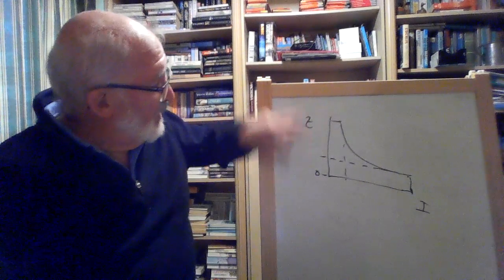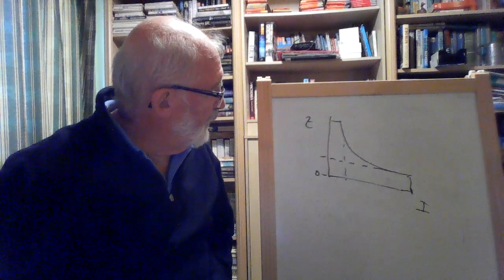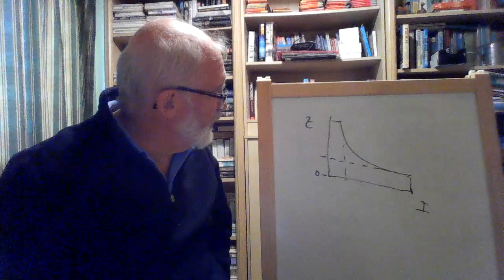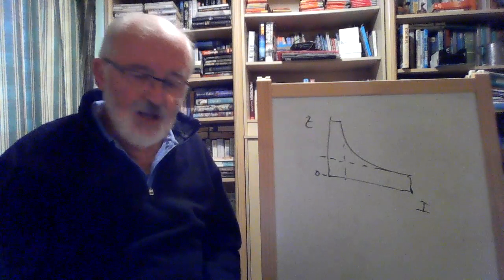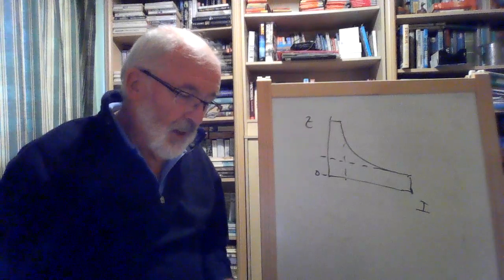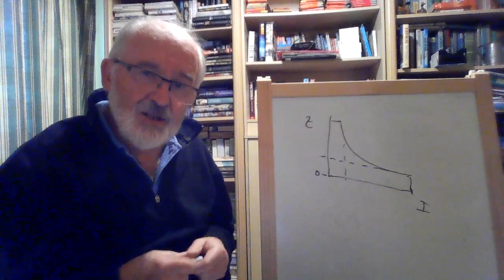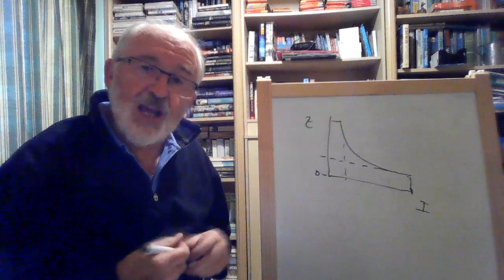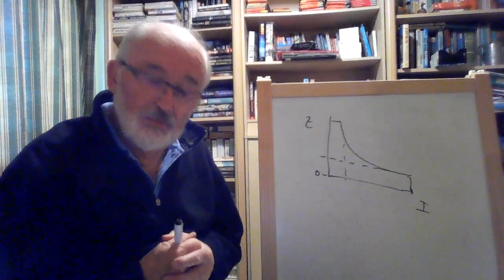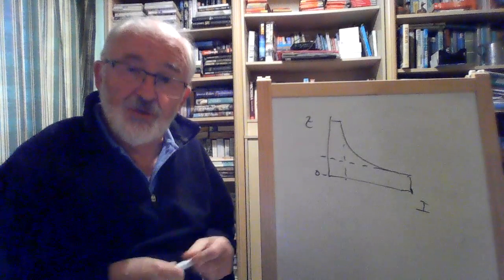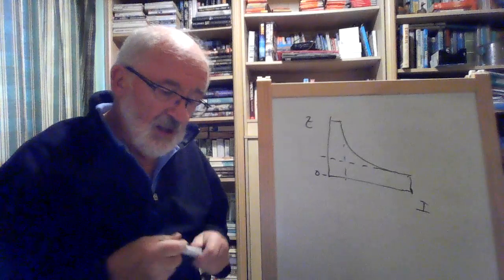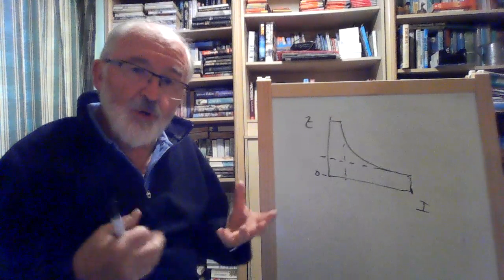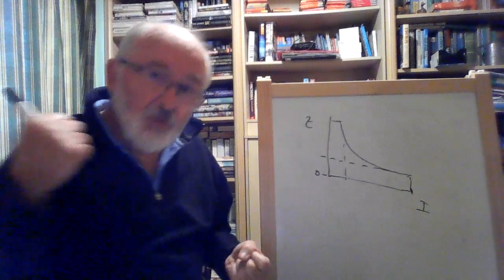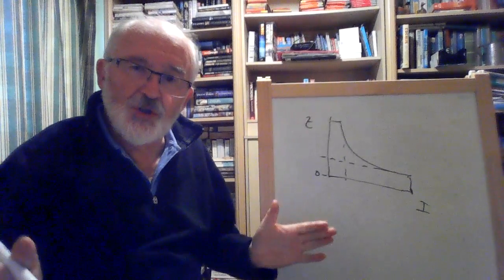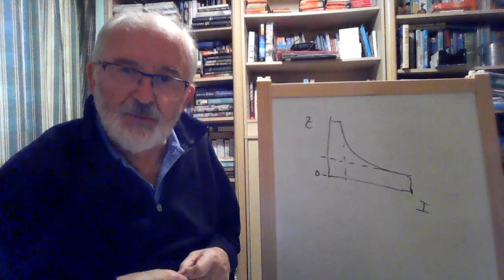Okay, now these times vary. It depends on the size of the voltages and the currents involved, but typically you're talking about a delay of maybe 1 to 20 seconds. Secondly, an instantaneous current trip protects against short circuit, where we get a very, very high current. You can get thousands of amps going through the system, and that will operate somewhere between 2 and 10 times the full load current, and it will bang it out, shut it off, probably in less than 1 second.